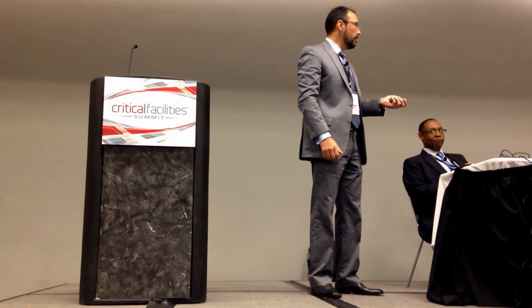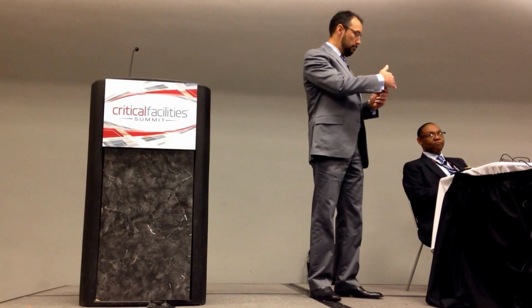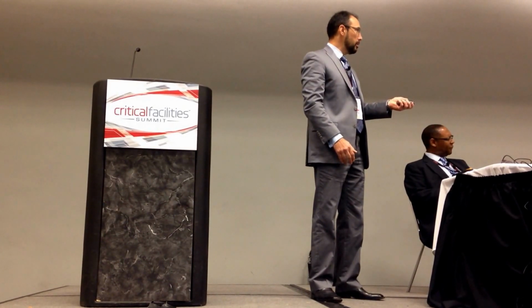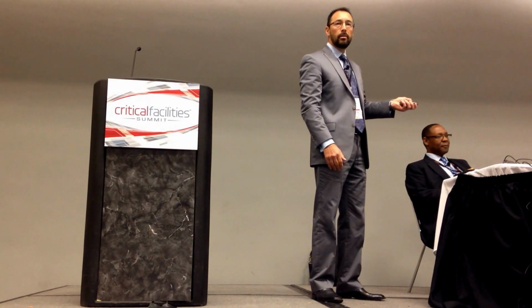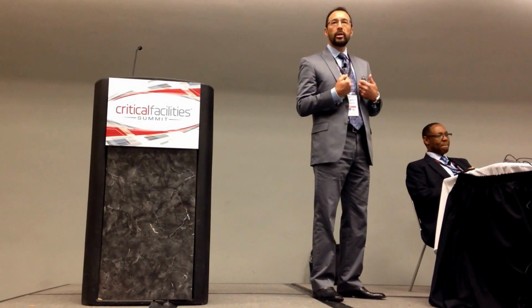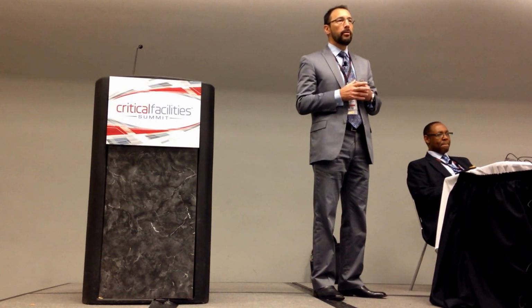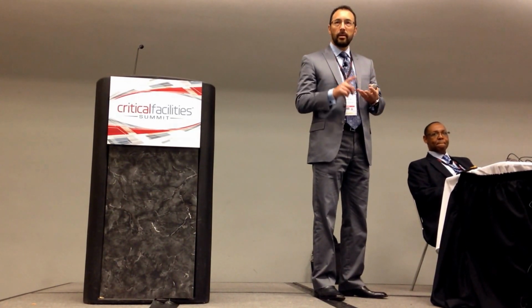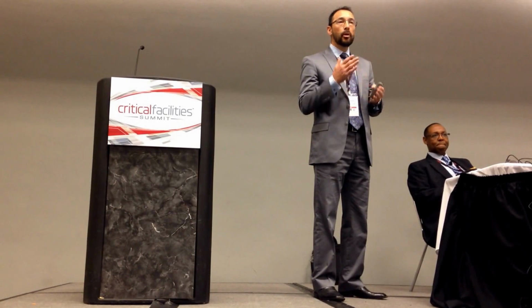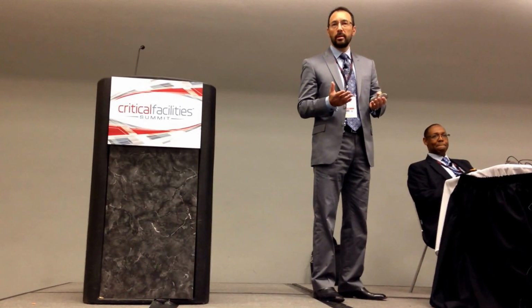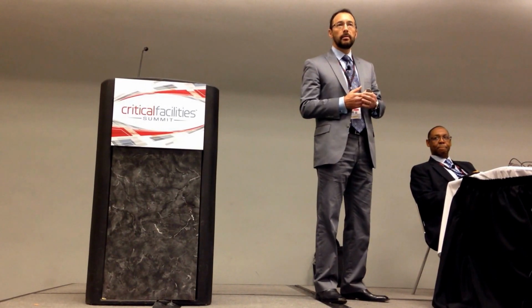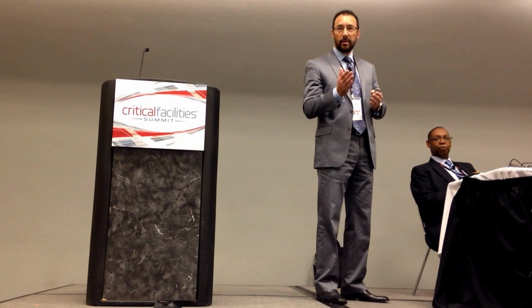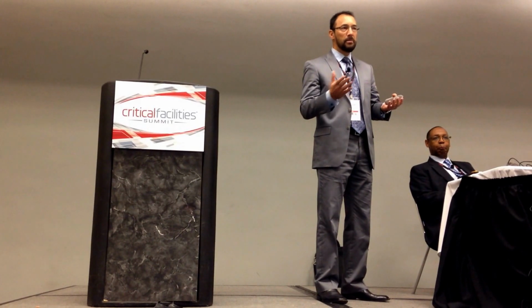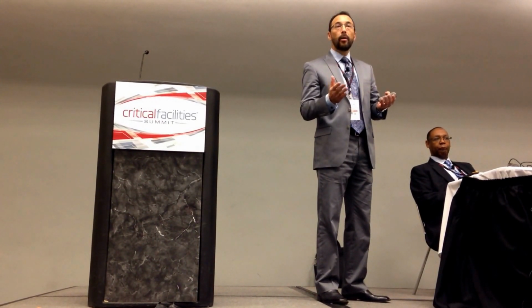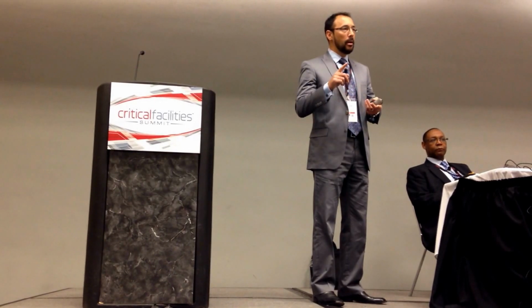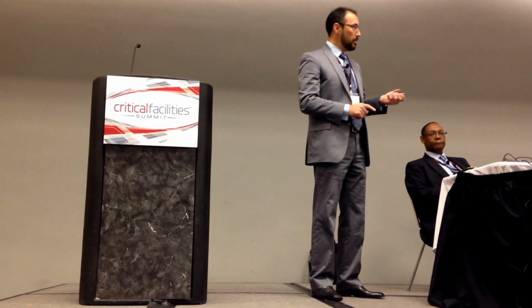Very often, the data center will never reach its capacity goal. What we see as an engineering firm is that, on average, enterprise, government, and colo data centers can get at most about 70% of the original intended IT capacity out of the room. They get stuck there — if it's a 1 megawatt facility, you can't get past 700 kilowatts without putting IT equipment in danger and incurring risk because of this problem.